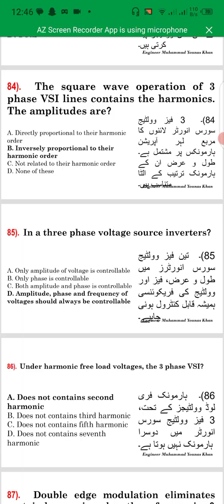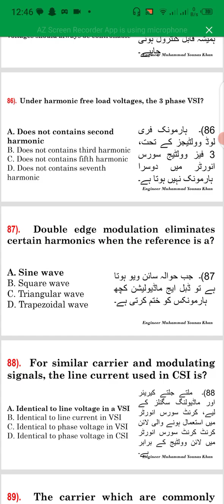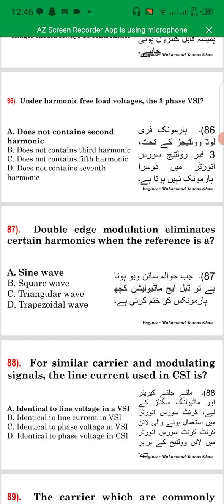Under harmonic free load voltage, the three-phase VSI does not contain the second harmonic, does not contain the third harmonic, does not contain the fifth harmonic, does not contain the seventh harmonic. Does not contain the second harmonic. Double edge modulation eliminates certain harmonics when the reference is a sine wave, square wave, triangular wave, trapezoidal wave. Sine wave. For similar carrier and modulating signal, the line current in CSI is identical to line voltage in VSI, identical to line current in VSI, identical to phase voltage in VSI, identical to phase voltage in CSI. Identical to line voltage in VSI.